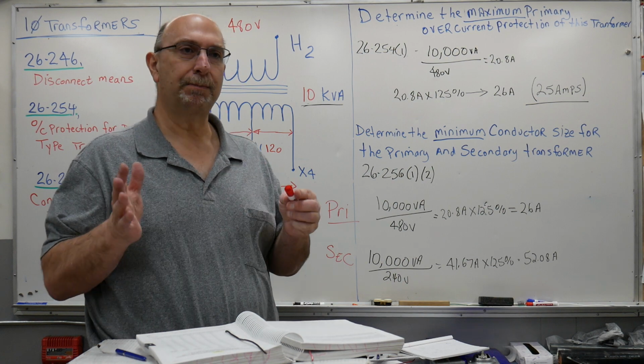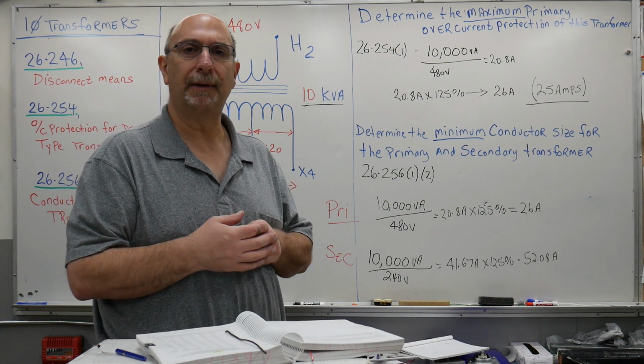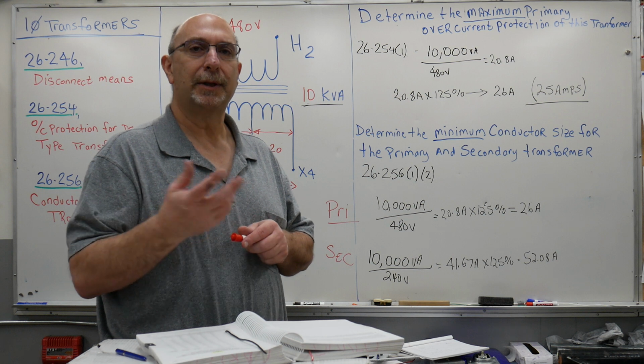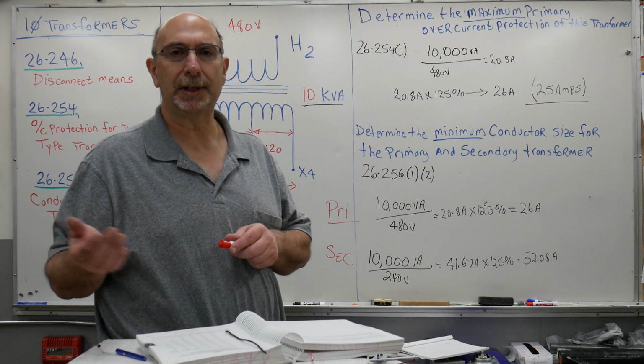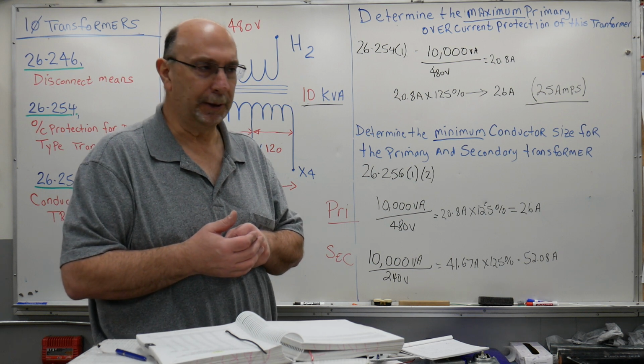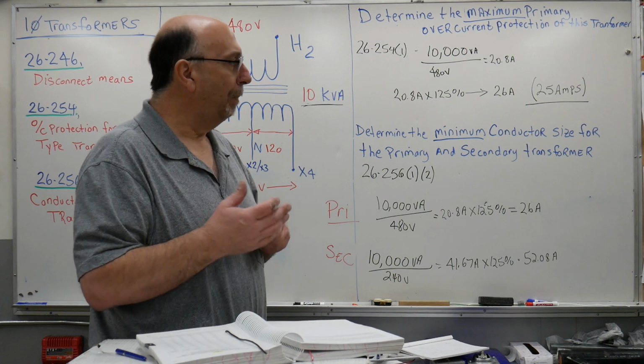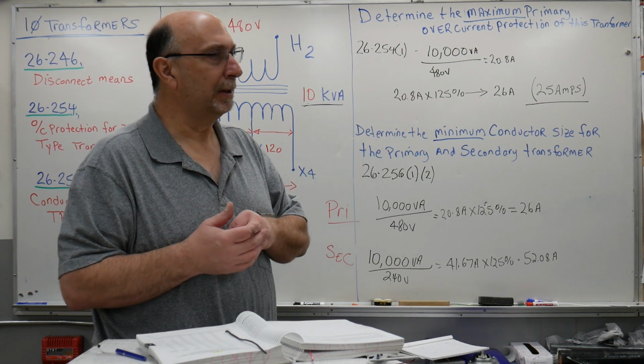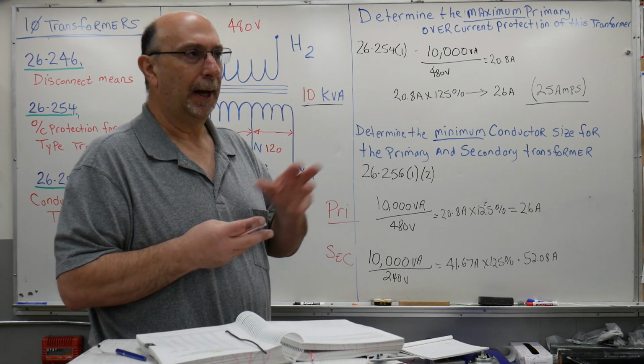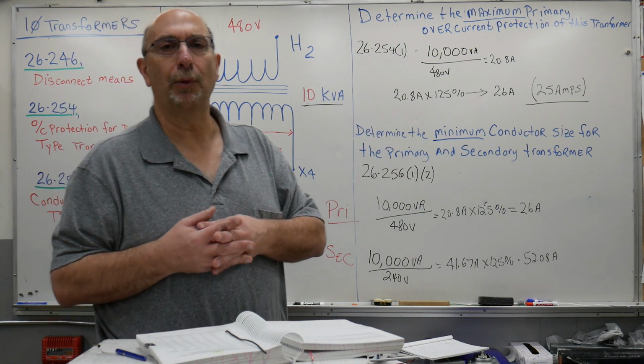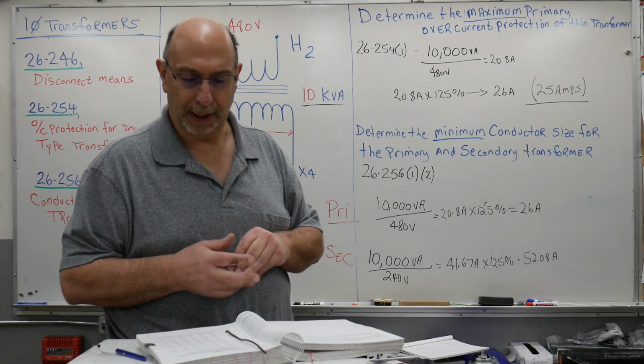When you look at pretty well 99% of electrical equipment, it is all marked with 60/75 degree conductor. We know panel boards are rated for 75 degrees C. Transformers are rated for 75 degrees C.